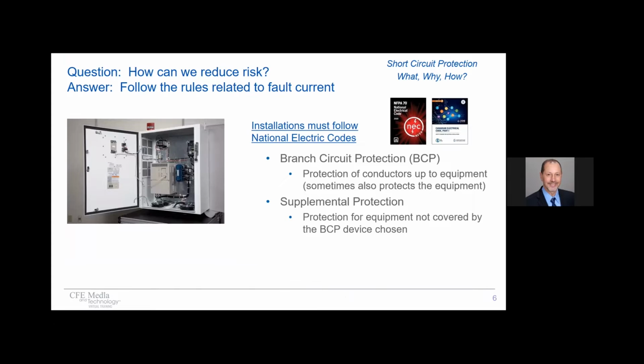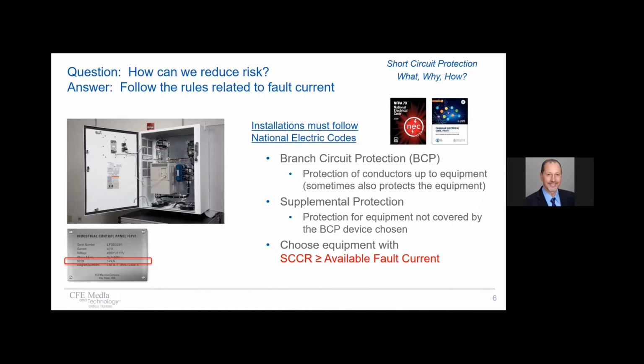But often, there's also supplemental protection that's required when what's being used to protect the branch circuit wiring does not actually protect the equipment. Additionally, the equipment must be chosen such that the withstand capability, or the short circuit current rating, is greater than or equal to what's available for fault current at that point on the system. And lastly, the instructions for any given equipment must be followed. So at a very high level, that's what we do to reduce risk. But in this session, we're really focusing on how that's related to variable speed drives.